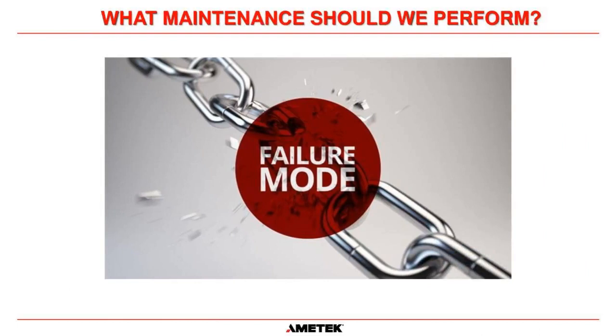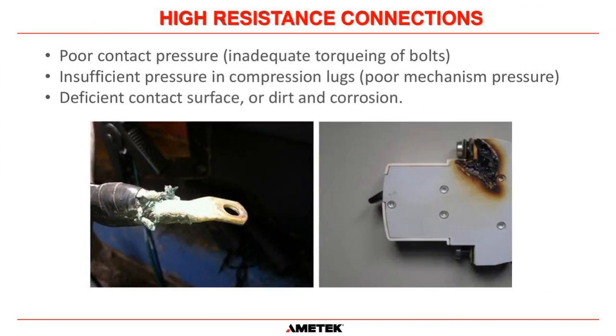So, what maintenance should be performed? Well, really, that depends on the failure modes. And what we did when we designed the maintenance schedule for our UPSs is we looked at the main failure modes and made sure that we were taking care of the things that could happen. Okay. So the first failure mode I'm going to discuss today is high resistance connections.